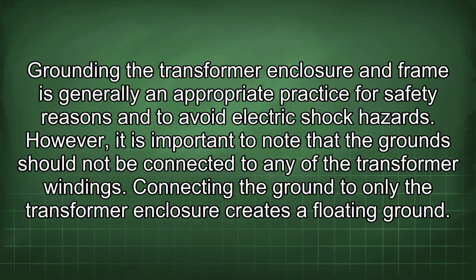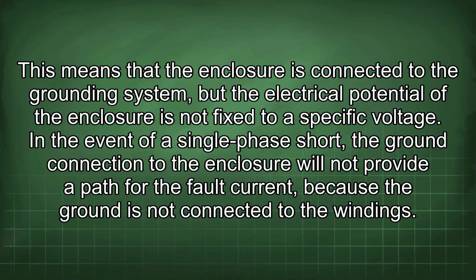Grounding the transformer enclosure and frame is generally an appropriate practice for safety reasons and to avoid electric shock hazards. However, it is important to note that the ground should not be connected to any of the transformer windings. Connecting the ground to only the transformer enclosure creates a floating ground. This means that the enclosure is connected to the grounding system, but the electrical potential of the enclosure is not fixed to a specific voltage.